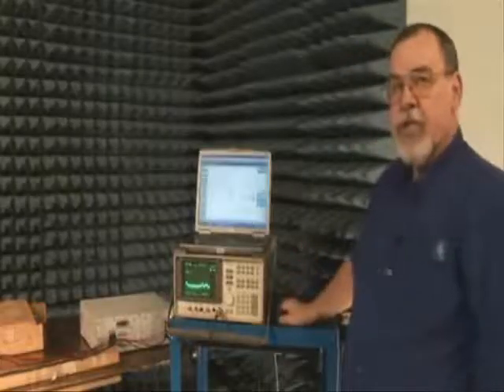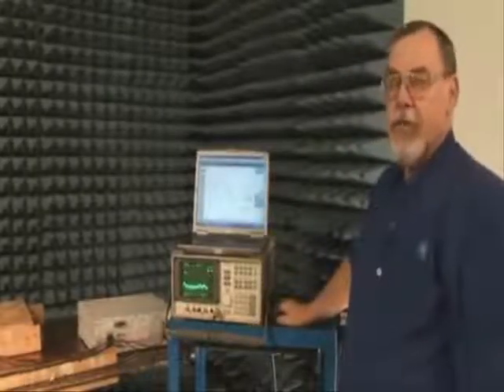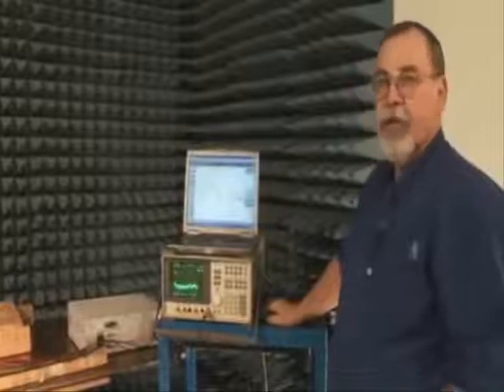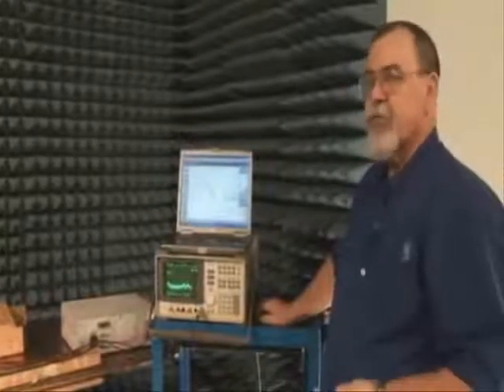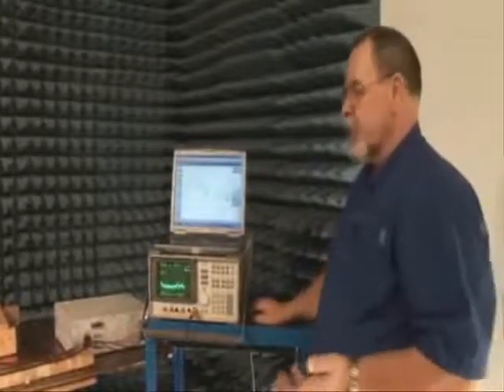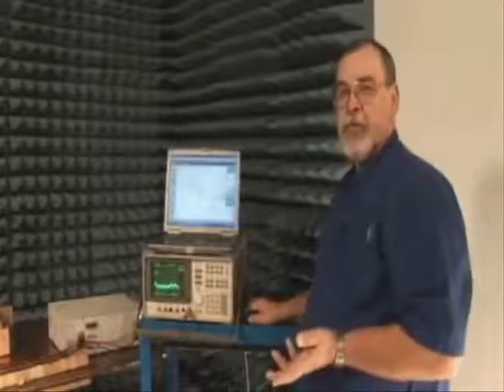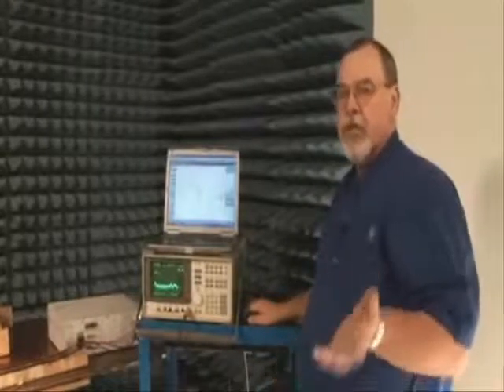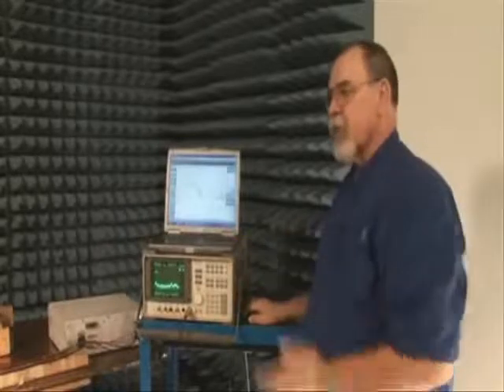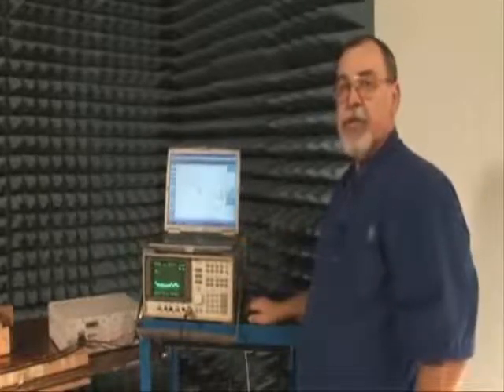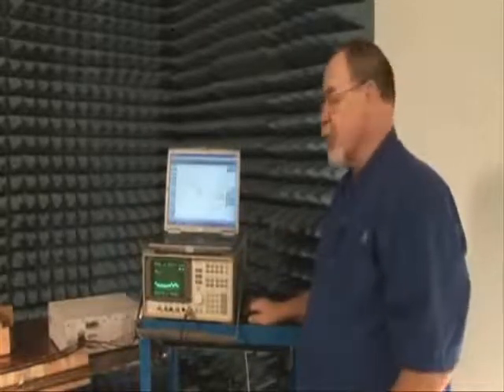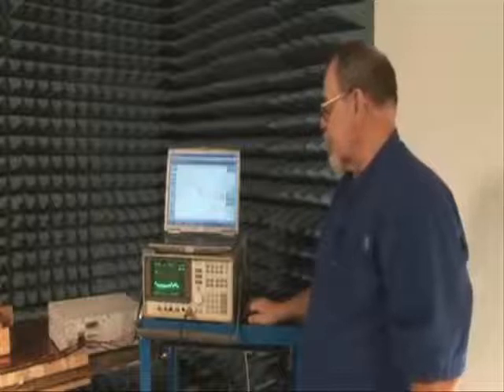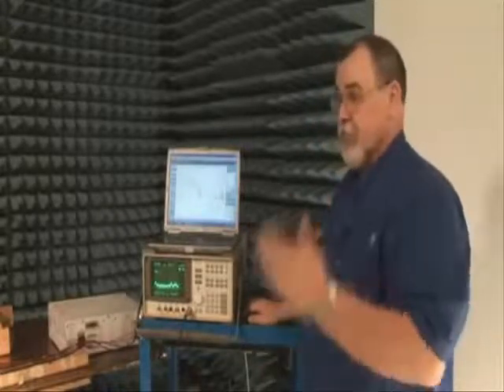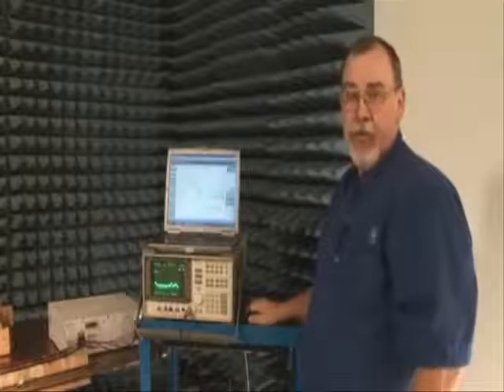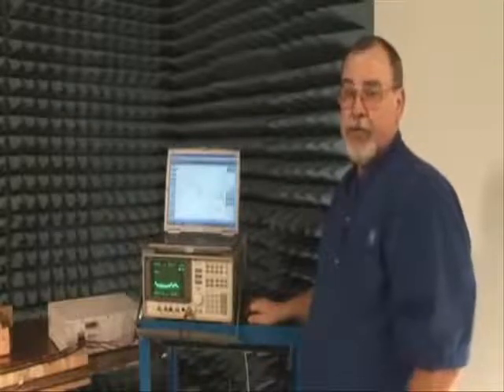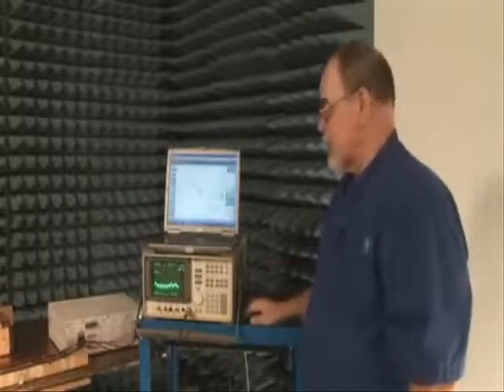We would do this test again on the neutral lead to be complete, and if we have to do all the phase leads, etc., so each individual lead. If we get into trying to find problems, sometimes we will use various techniques that we discuss in other areas regarding troubleshooting and using the probe for measuring things outside the normal test. However, this is the final test on that item, and we could repeat on the second item, but for this demonstration, we'll just limit it to the one test.